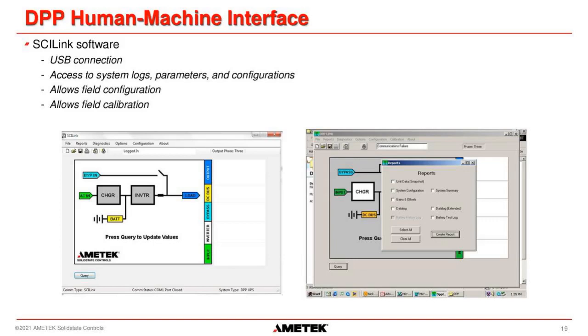So these are some screenshots from our SCI Link software. It uses a USB connection directly to the front of the UPS. And you can access system logs, parameters, and configurations. It allows for configuration in the field by our FSEs, and it also allows for calibration in the field.